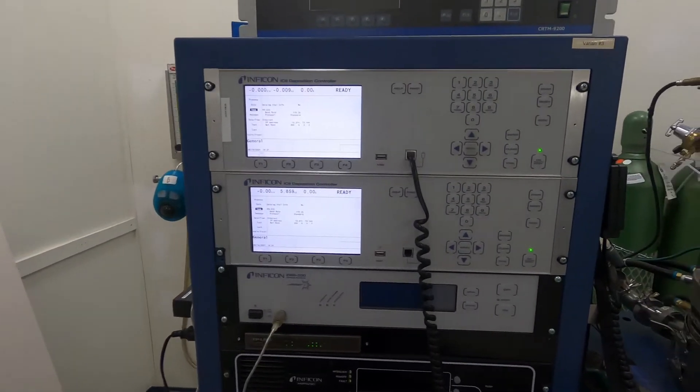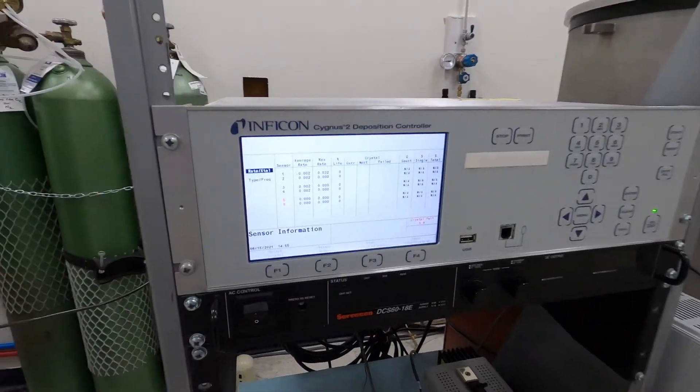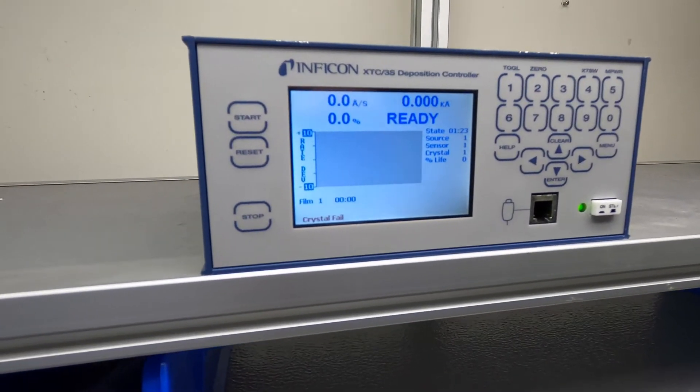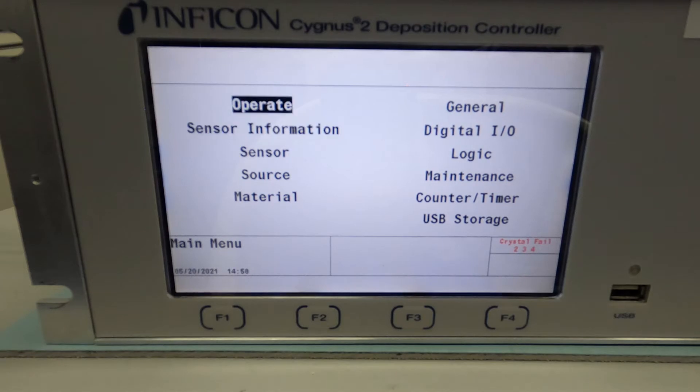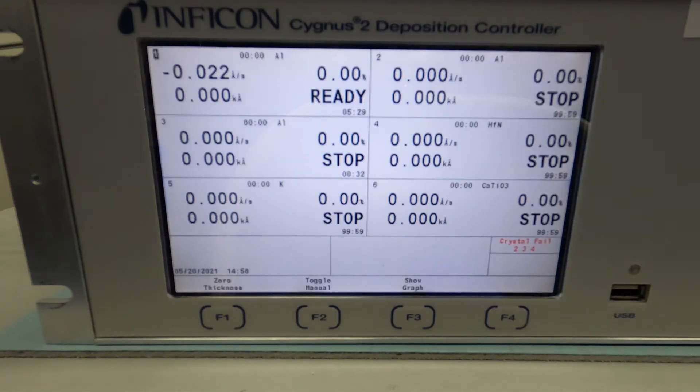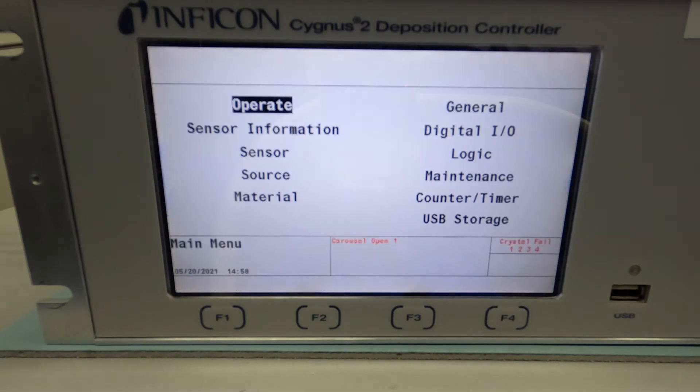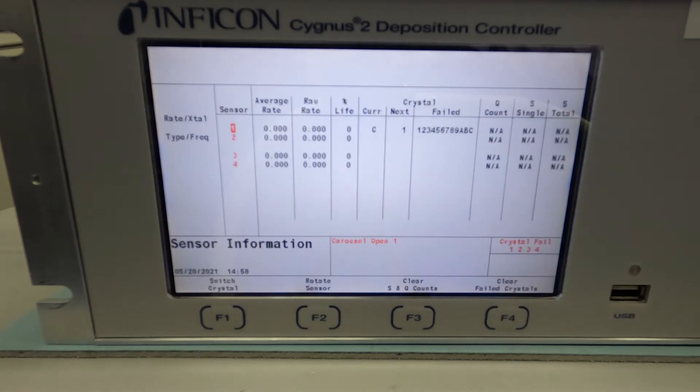Inficon deposition controllers such as the IC6, Cygnus 2, or XTC 3 with position feedback will automatically detect when a carousel is removed and display a carousel open message on the operating screen. When a carousel changeout occurs, all crystals will be identified as failed.